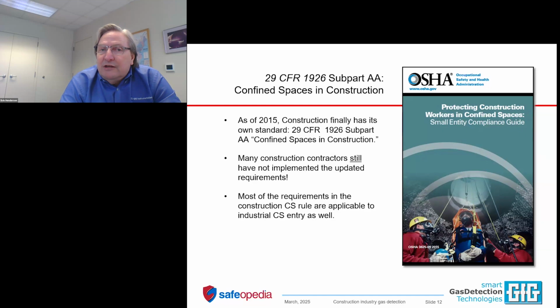In 2015, OSHA finally published 29 CFR 1926, Subpart AA, that's confined spaces in construction. So Subpart AA gives you a lot more information as to what comprises a confined space. It does not disagree with the general industry guidelines for permit confined space entry.